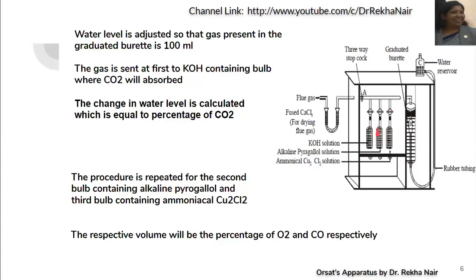From all three bulbs, by noting the change in water level readings, we can calculate the amounts of carbon dioxide, oxygen, and carbon monoxide. The unabsorbed gas is considered as nitrogen. Starting from 100 ml, whatever amounts of carbon dioxide, oxygen, and carbon monoxide have been calculated are subtracted from 100, and that gives the percentage of nitrogen present in the flue gas. Thank you, that's all for today.